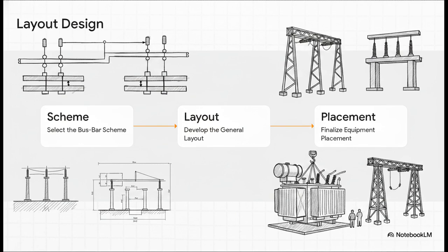Step 1: selecting your busbar scheme, basically the skeleton of your substation. Will you use a 1.5 circuit breaker scheme for maximum reliability, or a double main scheme? Once that's nailed down, step 2 is developing the general layout, or GLO, alongside detailed plan and section drawings. Step 3 is the exact placement of massive heavy machinery.